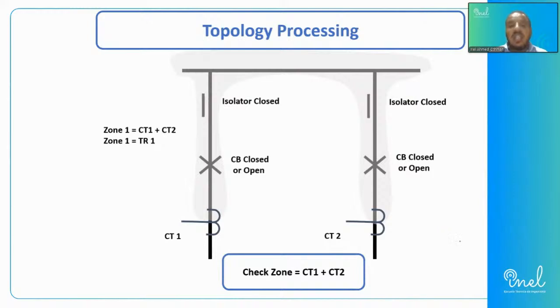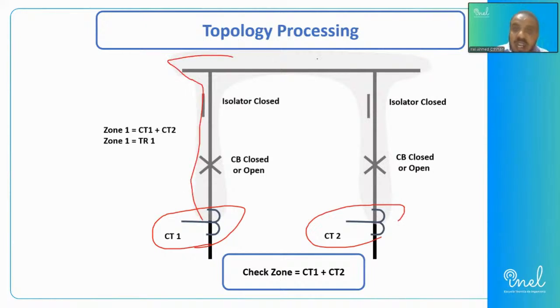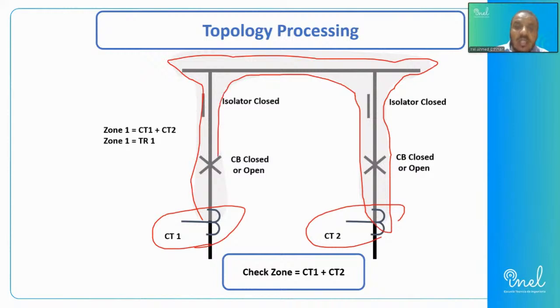differential protection. And here again, we have a certain CT1, and we have a certain CT2, and we have a shaded area here. If you see, there is a gray area here, which I am trying to put a border around. That gray area between CT1 and CT2 is the protected check zone. So we are checking and protecting such a zone to act like a differential protection for that zone. So the protected zone is the shaded one, and now I am putting some red border around. That is the area which you are protecting.